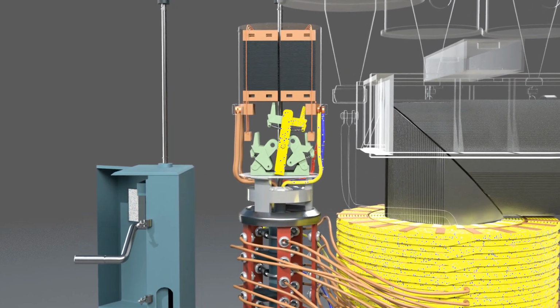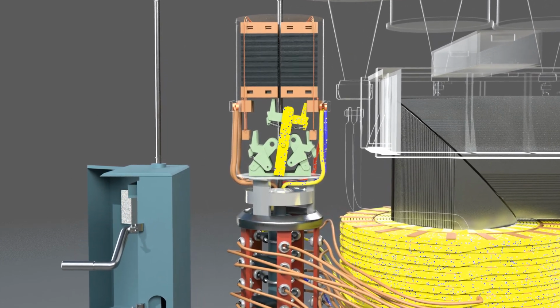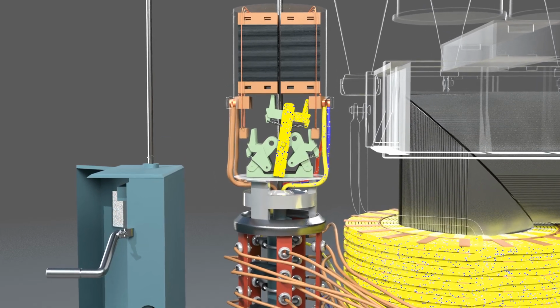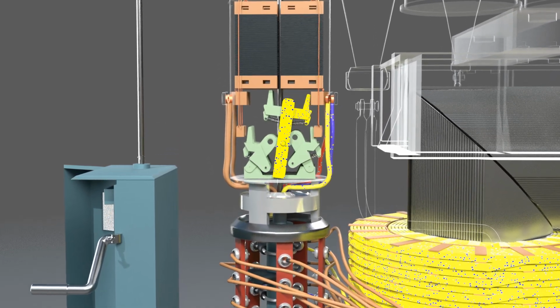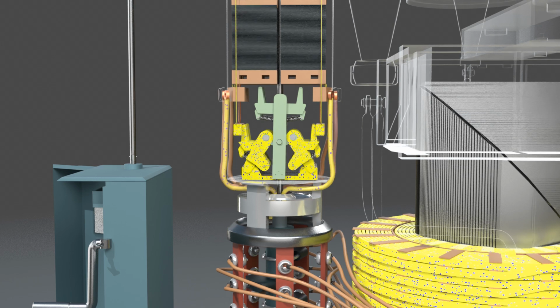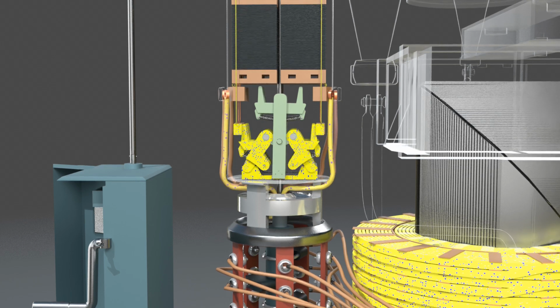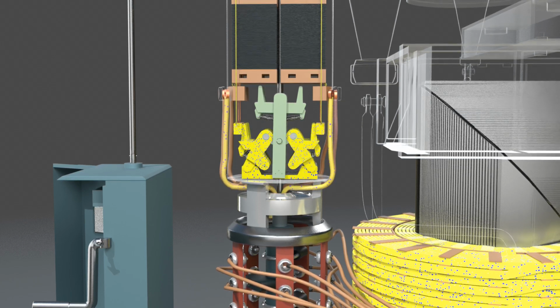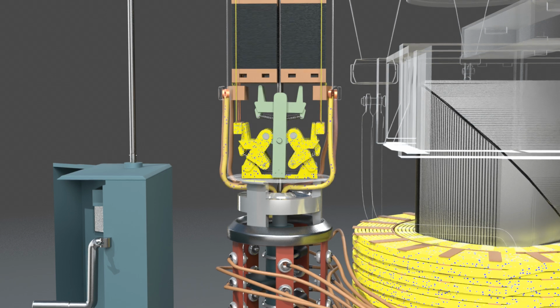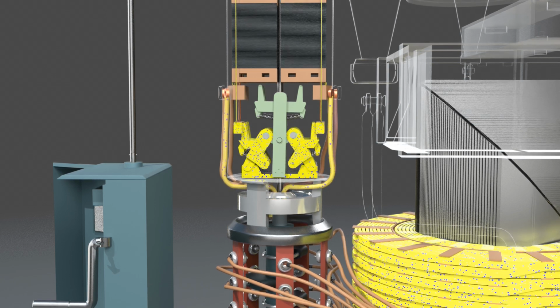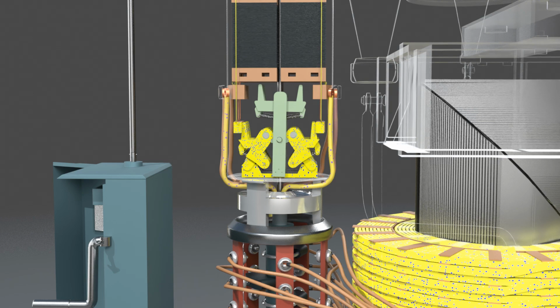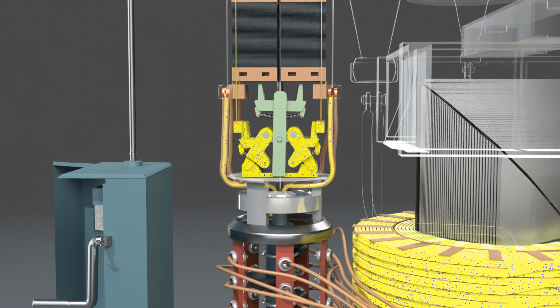Transition process. During the tap change, as the arm moves from one tap to another, it passes through a center position where the current flows through a transition resistor. This transition resistor helps to limit the circulating current, prevent arcing, and ensure a smooth and reliable transition between taps.